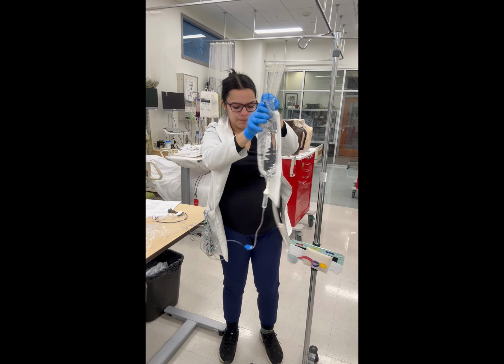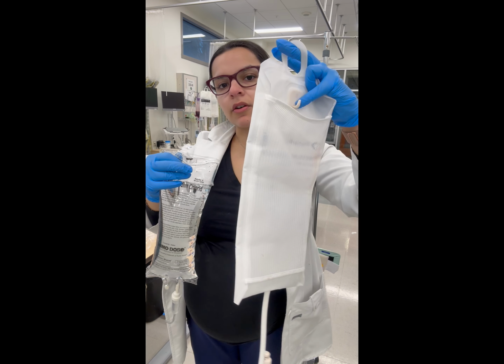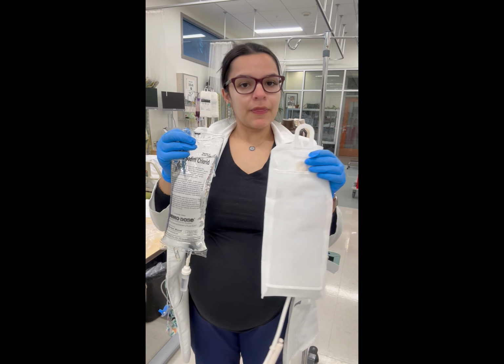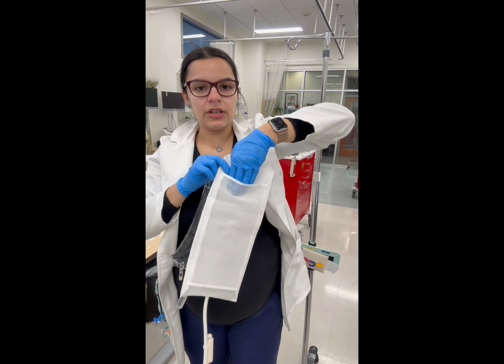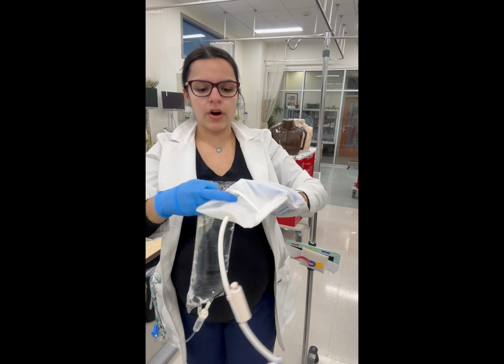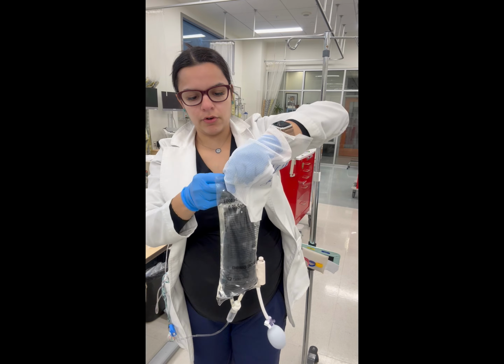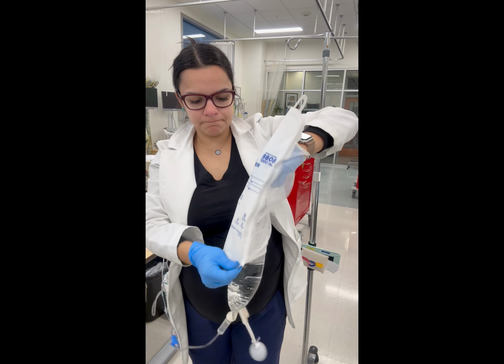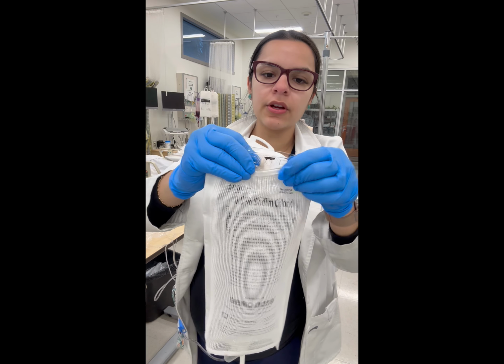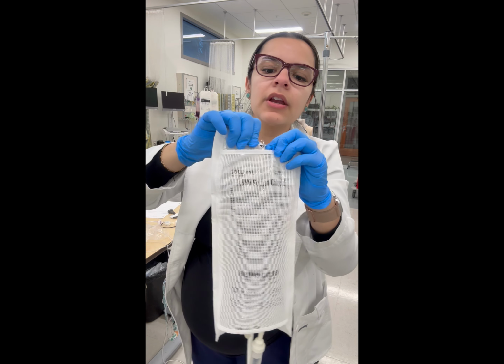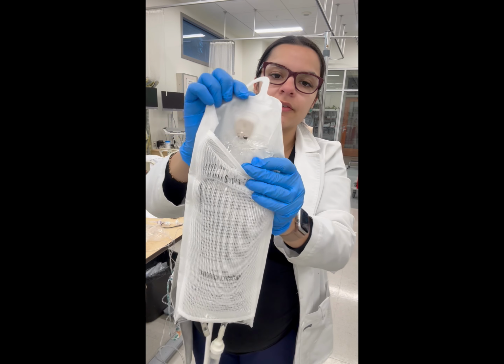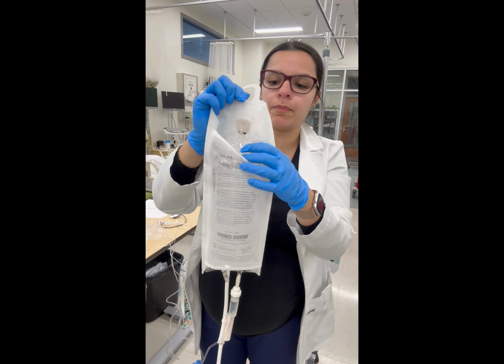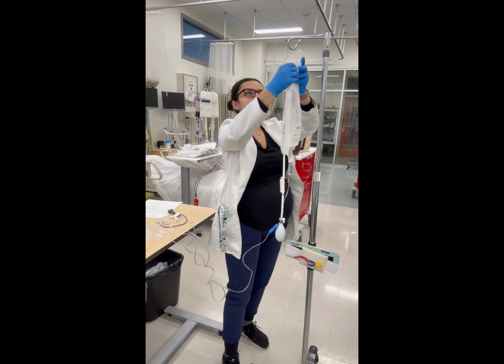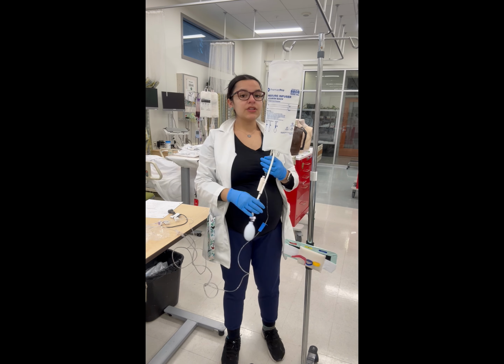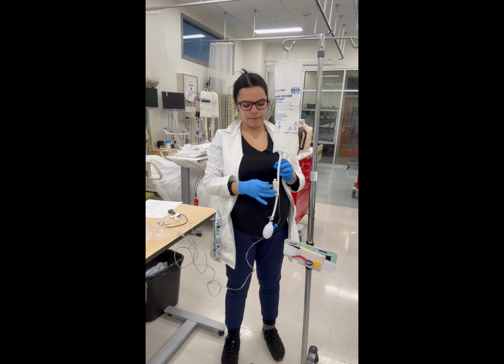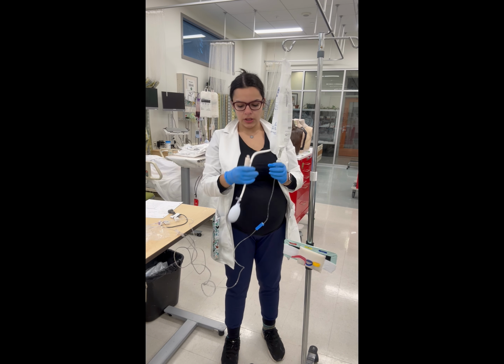So you're going to take this off the pole. And if you notice on the bag here, there is a little hanger, okay? I am not the most coordinated individual sometimes, so I actually place my hand through the bag and grab the bag from the bottom to pull it through. Okay. Once I pull the bag through here, I'm going to want to use that little notch to hang up my bag inside of there, okay? It's like a little IV pole inside of the pole, okay? Once I've done that, I can come back over to my pole. Remember, we need to pressurize this to 300, and we will see that green notch light up here, okay?